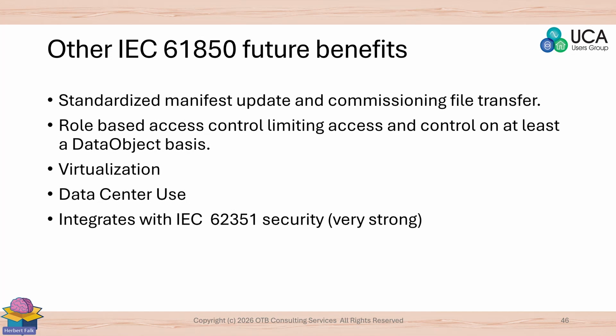If you take a look and read about the VPAC Alliance, 61850 is the core technology for virtualized protection. It's being used in substations for data centers, and it integrates with 62351 security.